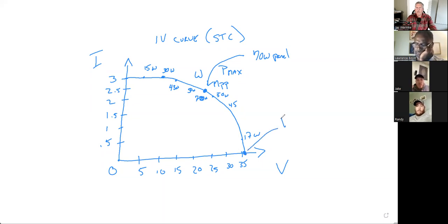And that would be at VOC. It's the theoretical maximum number of cars, but nothing's moving. So in this case, it's the theoretical maximum voltage, but there's no power. It's at 0. Nothing is moving. Same thing over here. The ISC is the theoretical maximum amperage, but there's no power. So both of those conditions are bad. You don't want your system operating there.